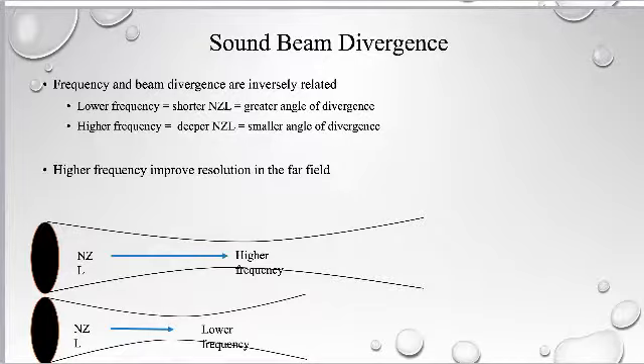So are crystal diameter and frequency directly related? You just said that crystal diameter and beam divergence are inversely related, and so are frequency and beam divergence. They're both inversely related. Crystal diameter and frequency are not related. And that's where a lot of people make a mistake. Crystal diameter and frequency are not related. They both contribute to the shape of the beam, but they're not related. What is related is crystal thickness and frequency. Okay, thank you.